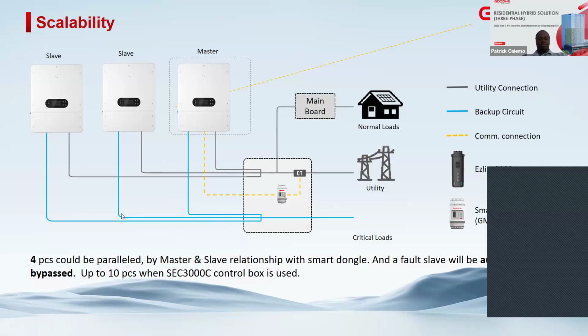Now on the backup port, same thing, it branches out to each inverter. So if you have critical loads connected in the backup port, all the inverters will be outputting the same amount of power to support that load. If it's a 30 kilowatt load, then all the inverters will be outputting 10 kilowatt to support that load. If you also have loads on the on-grid port, probably 10 kilowatt or something, then each inverter will be outputting around 3.3 to support the loads on the on-grid port. So that's a way in which you can connect 1 to 4 pieces.